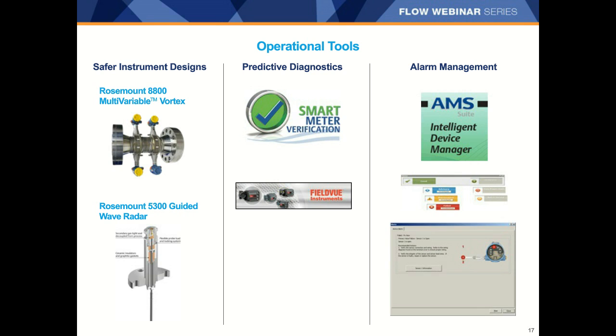You can define test schemes, schedule calibrations, and manage calibration data. You can easily filter alerts based on severity, location, or tag to quickly determine maintenance activities. And you can enable automatic generation of a historical record for each device maintenance activities, or essentially an audit trail. And as with all Emerson products, AMS Device Manager has been designed based on human-centered design principles, ensuring intuitive graphics and easy navigation for all levels of users.